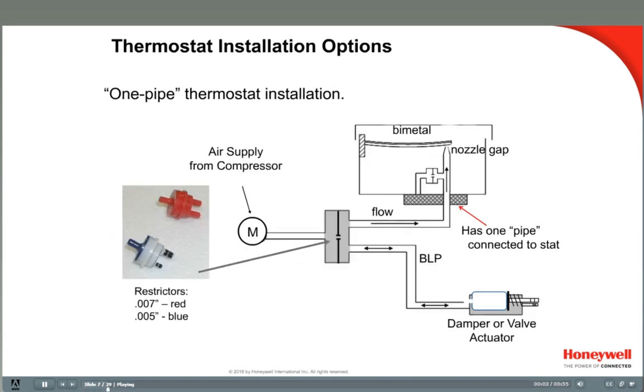This diagram represents a one-pipe thermostat installation — same thermostat, just a different installation. In a one-pipe installation, the restrictor, obtained separately, is in the main air supply, not inside the thermostat. The main air port on the stat is blocked, but the nozzle flapper operation remains the same. All the air lines after the restrictor will assume the air pressure value that develops at the thermostat's nozzle. So the air pressure in the stat is also the air pressure in the branch line and in the actuator, and a valve or damper connected to this actuator will modulate in proportion to the room's temperature change.